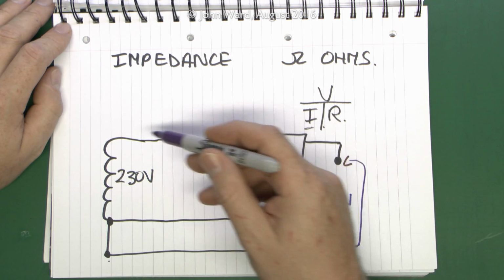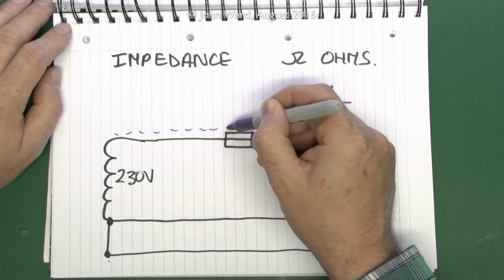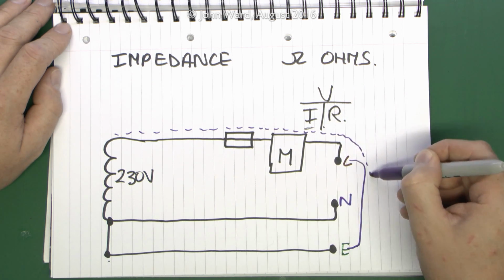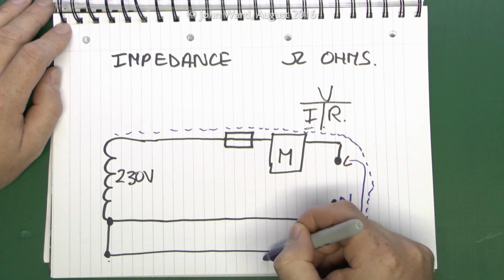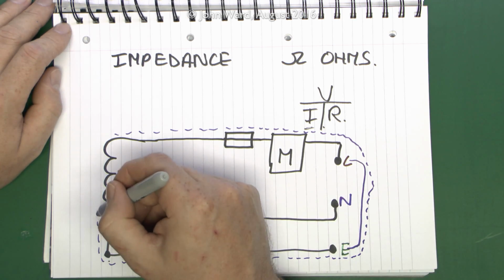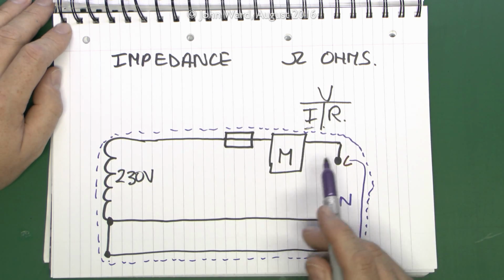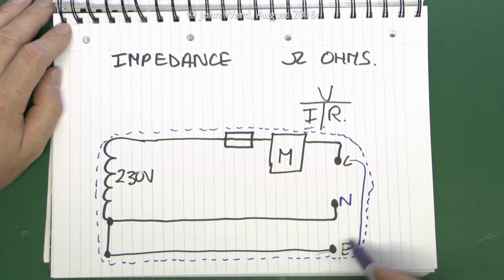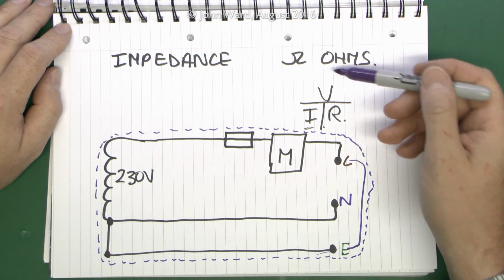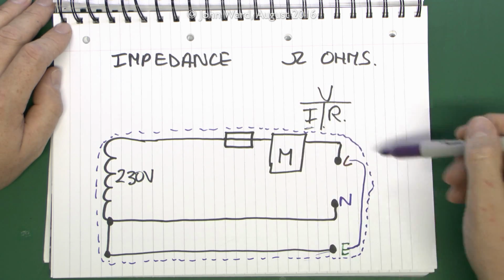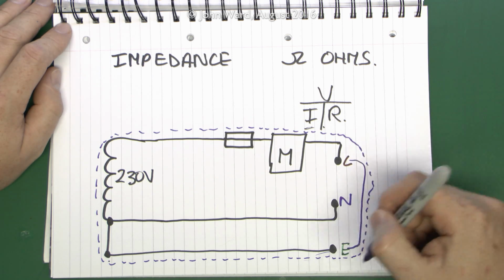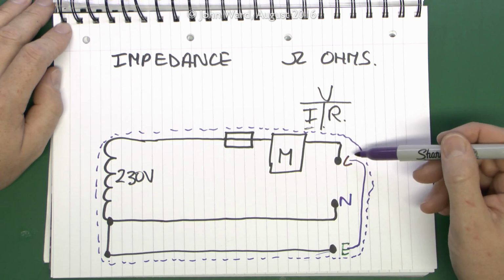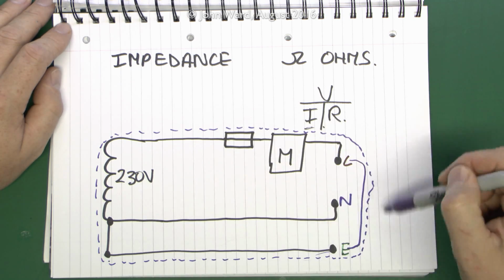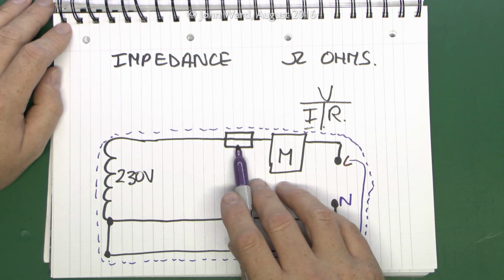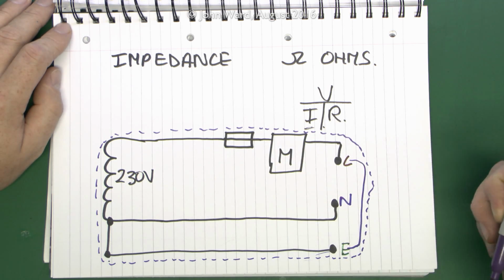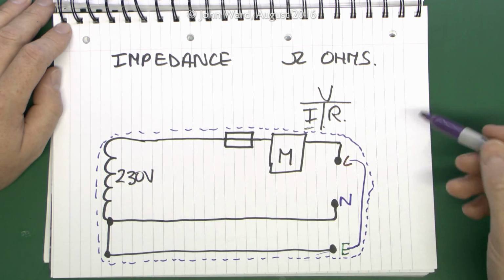So the loop then is the entirety of this. So it's all the way from the transformer here through the wiring and the fuse and electricity meter and what else you've got, through the fault, and then returning along the earth conductor here, all the way back to the transformer. So what we need to find out is essentially the resistance or impedance of this entire circuit, and then simply by dividing voltage by the impedance, we can establish the sort of current which will flow in the event of a fault. And it's important to know this because we need to make sure that if this does occur, the current that flows is sufficient so it can actually blow the fuse and disconnect before the cables and things melt or set on fire. Now, for this particular impedance here, impedance has the symbol Z.